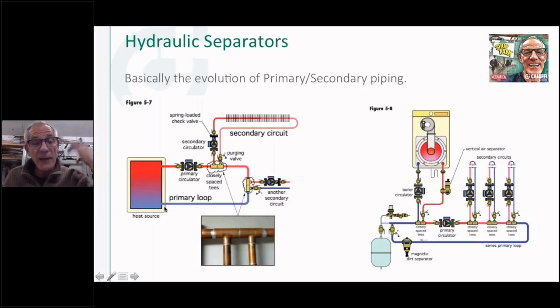Yeah, in this basic, what I consider this is the boiler is within the primary loop. So I would probably put the air purger right here. In fact, I'd probably have an air separator there, and that would be one of the cases where you might put the air separator and the expansion tank in one package right there. So then this circulator is pumping away from it, and through this piping here, these circulators will also pump away from it. So you establish your point of no pressure change. I should probably put that in there, but I was trying to keep the drawing simple to show the closely spaced T's. But that's a great question, and you'll see more of that as we go through the drawings.